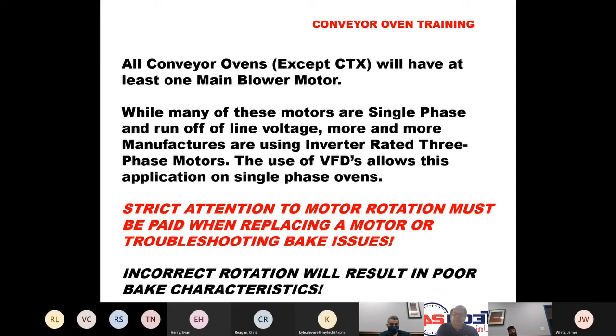VFDs, and I'll talk more about these in the Middleby section. Some people call them inverters or a variable frequency drive. They're capable of taking a single phase input and creating a three-phase AC output to run a three-phase motor. And so if two of those motor leads get reversed, it changes the rotation of the motor.